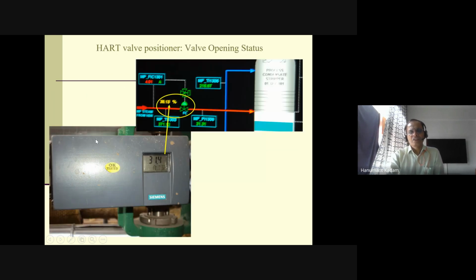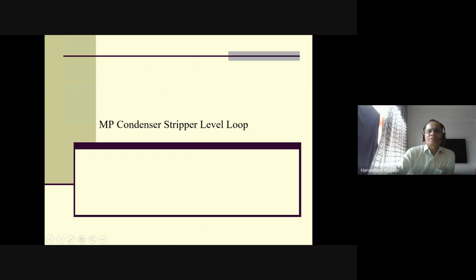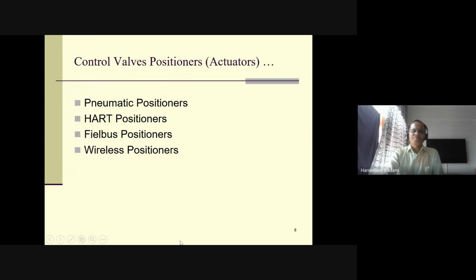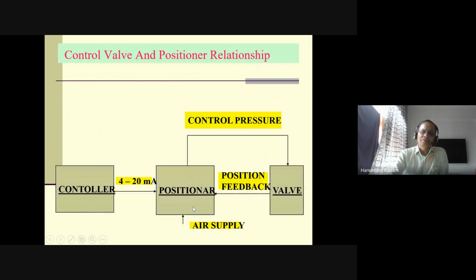And this is the electronics of the HART positioner, which is indicating your percentage valve opening here. And this is the graphical screen on the DCS. Now we'll see one by one. First, we'll see the pneumatic positioner, then the HART positioner, then Fieldbus. And this is the way evolution has happened in the industry. So the latest is the wireless.